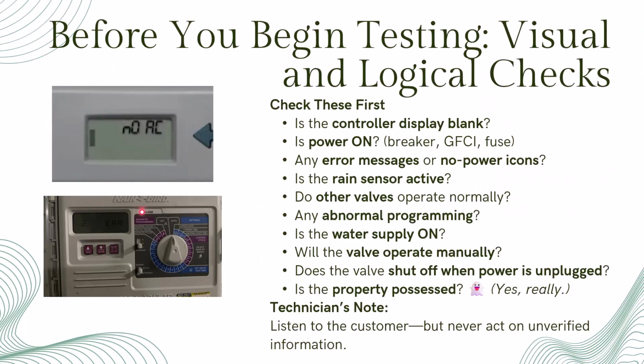Before reaching for the multimeter, start with basic visual and functioning checks. Look for obvious clues, a blank controller display, a tripped breaker, or a rain sensor that's still active. Sometimes the simplest oversight, like the water supply being off, can save hours of testing. If a customer or another technician shares details about the issue, always listen respectfully, but verify everything yourself. Never act on secondhand information unless you can confirm it firsthand.